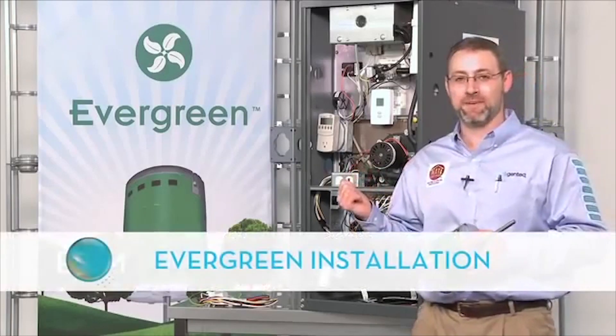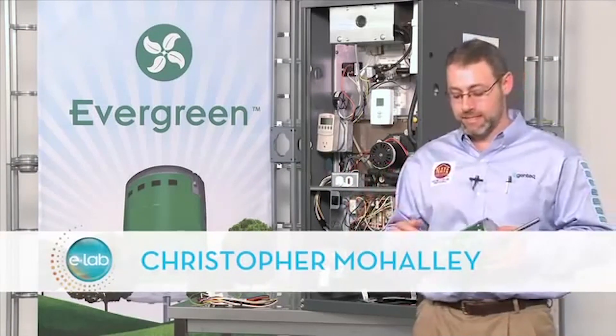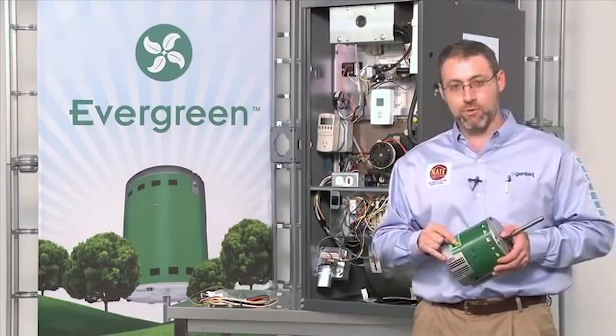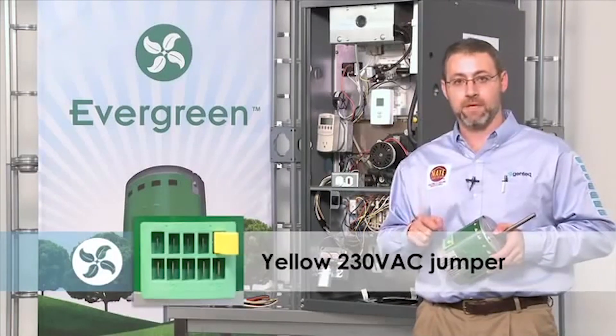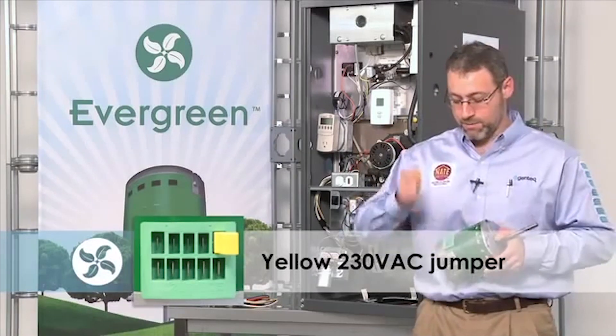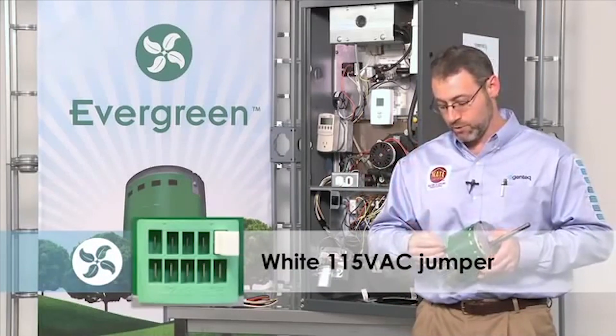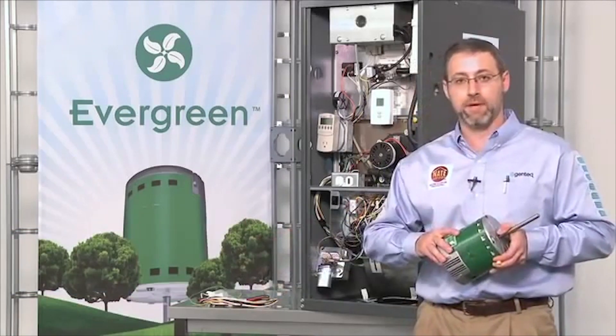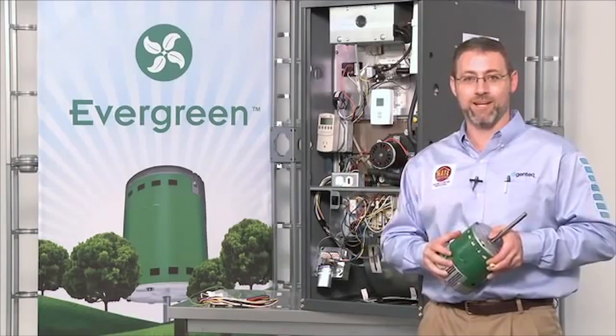Here we have a system that used to have a PSC motor and I've already gone ahead and installed the Evergreen motor into it. Before I did that I had to select the voltage jumper for the system. The motor ships from the factory with the yellow 230 volt jumper. If I want the motor to run at 115 volts, like for this furnace behind me, I simply remove the yellow jumper and put in the white 115 volt jumper. After installing the white 115 volt jumper I'll put the two harnesses back on the motor and then I'm ready to wire the motor to the system, which is what we're going to do right now.